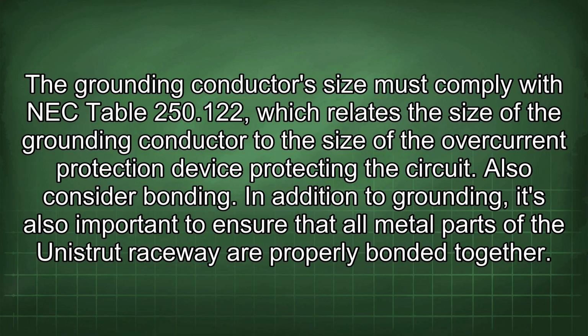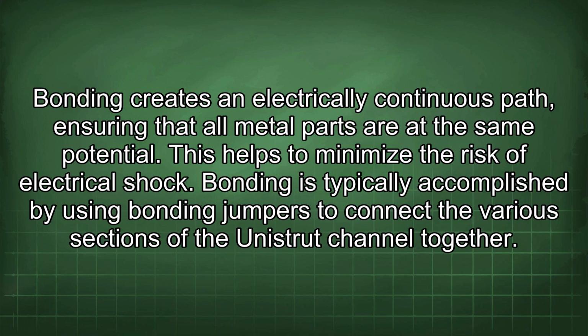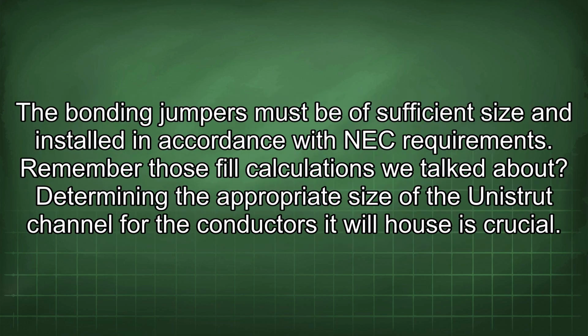Also consider bonding. In addition to grounding, it's also important to ensure that all metal parts of the Unistrut Raceway are properly bonded together. Bonding creates an electrically continuous path, ensuring that all metal parts are at the same potential. This helps to minimize the risk of electrical shock. Bonding is typically accomplished by using bonding jumpers to connect the various sections of the Unistrut channel together. The bonding jumpers must be of sufficient size and installed in accordance with NEC requirements.